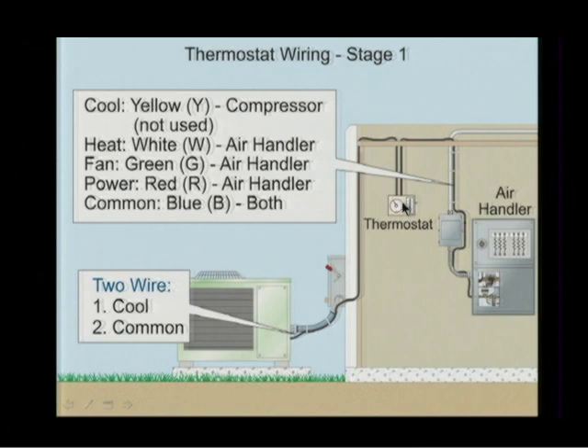So the way a thermostat works is that when it goes to heat, it closes two sets of contacts. It closes the contacts for the W, for the heat, but it simultaneously closes the green contact in the thermostat so that the fan is going and the heating is going at the same time. When we go to the compressor mode, where the thermostat says cool, it gets voltage to the relay for the compressor. At the same time, it energizes the green wire, closing the fan so that the fan works at the same time the compressor works. So the fan goes with the compressor, the fan goes with the heat, so it's going to run in both. And that's the simple basics of a basic thermostat.